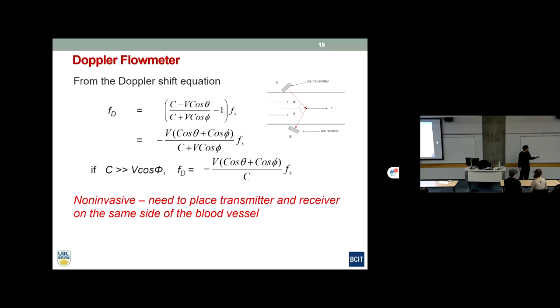Looking at this equation: the Doppler shift FD equals V times (cosine theta plus cosine phi), divided by C (the speed of sound), times FS (the source frequency). C and FS are constants; cosine theta and cosine phi can be fixed by placement. So FD is proportional to V, the blood flow velocity. For a non-invasive device, we cannot place transducers on opposite sides, so both the transmitter and receiver are packaged together on a single chip, and the reflected ultrasound comes back to the receiver.